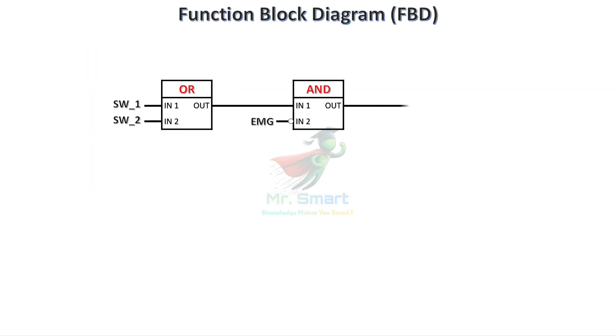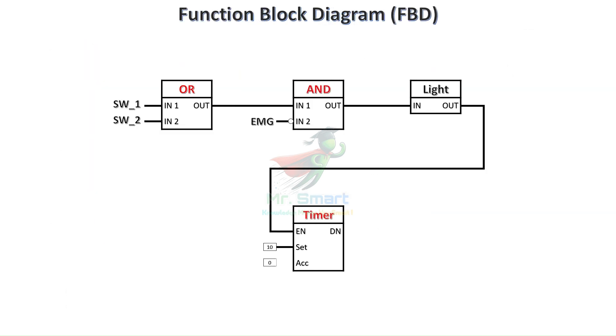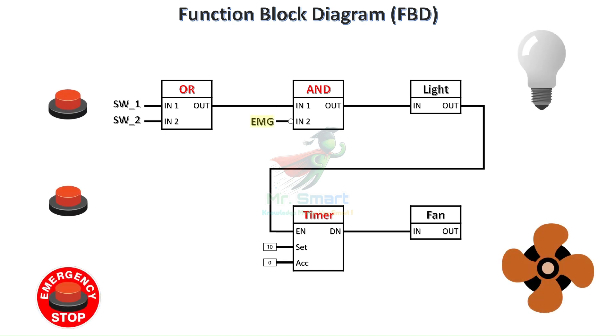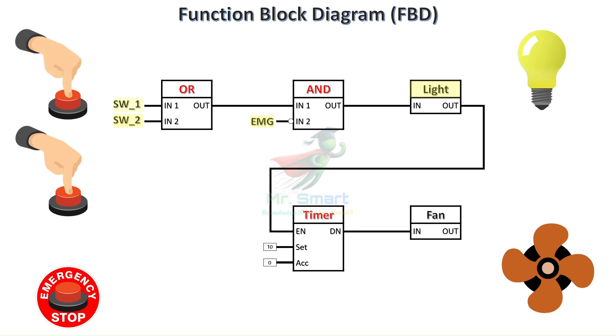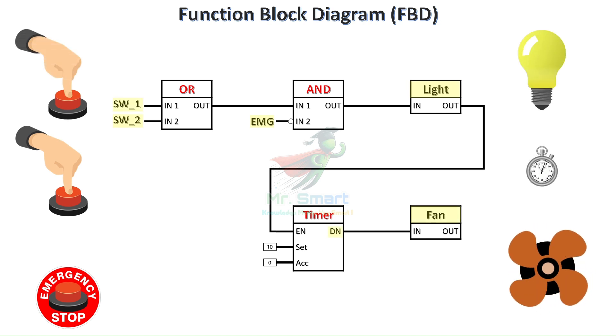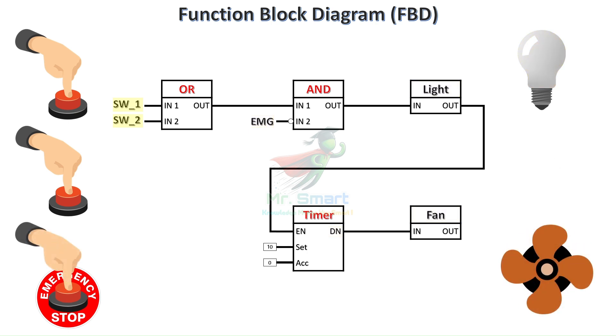Function block diagram, or FBD, uses graphical blocks to represent different functions like timers, counters, and logic gates. Each block has inputs and outputs that connect to other blocks, creating a flow of information. FBD is particularly useful for engineers who think visually, as it's easier to see the overall process at a glance. It's ideal for complex control systems like PID controllers, signal processing, and batch processes in industries.